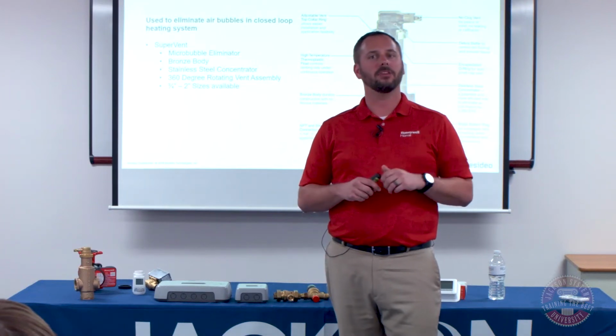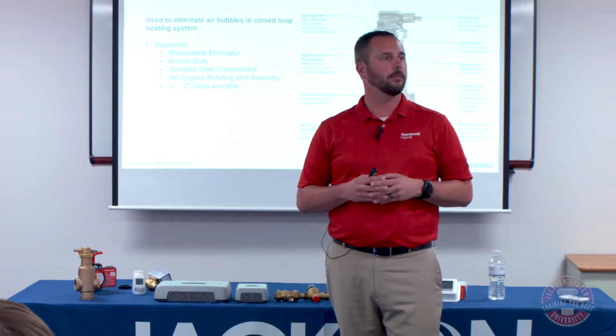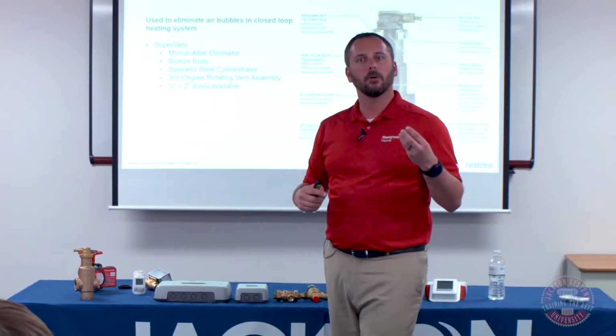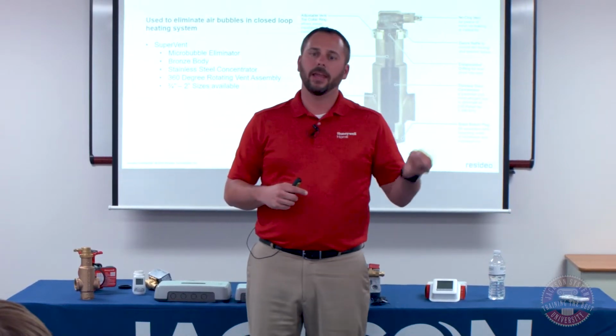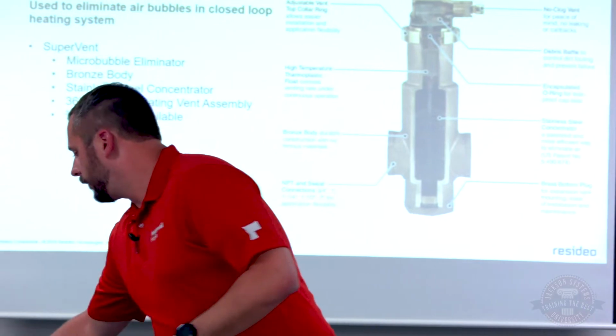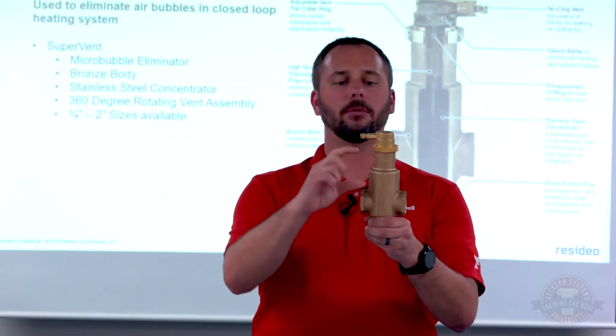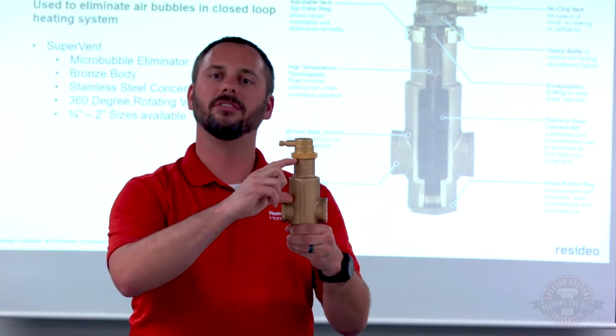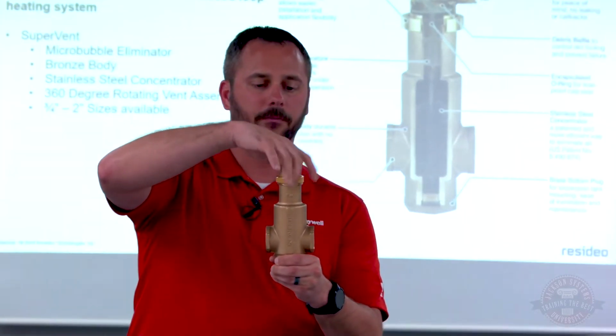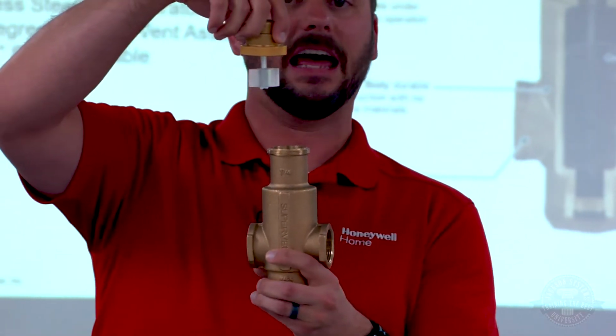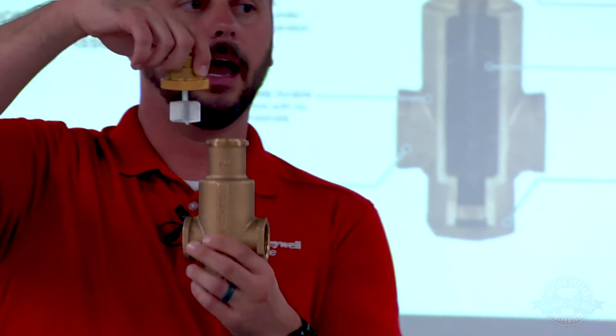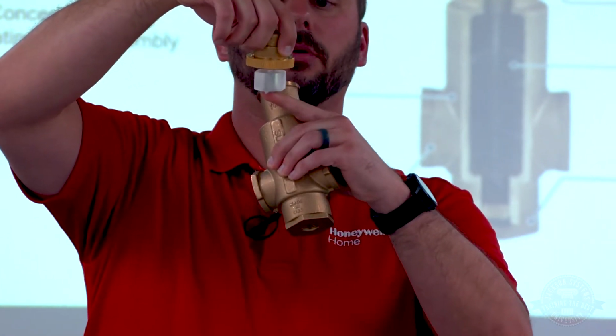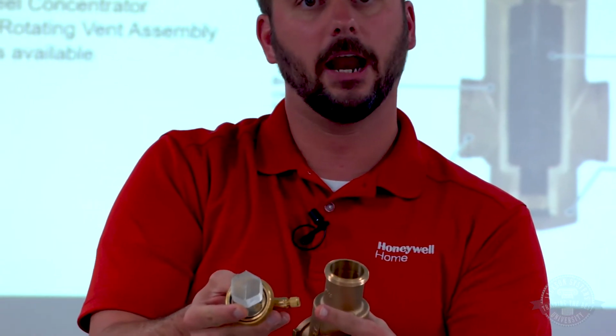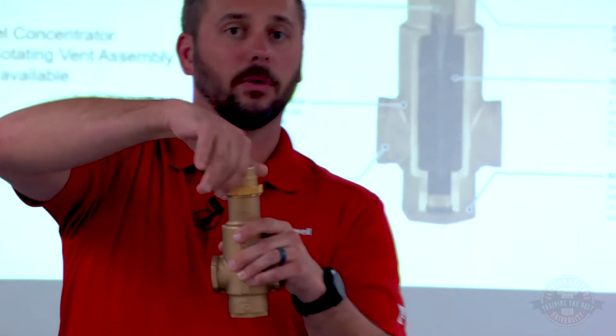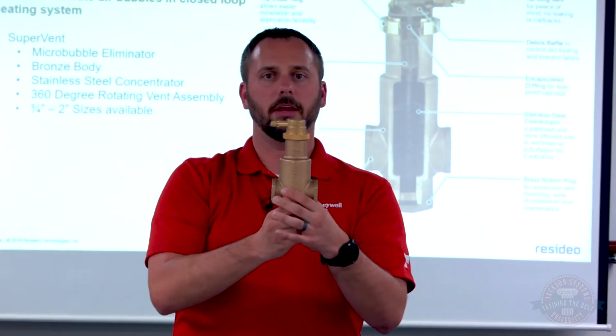What happens with this is we have a coalescing media that looks like a stainless steel brush inside of it. As the water passes through here, any of those micro bubbles get stuck on those bristles, and they end up purging their way up to the top. Once those micro bubbles start to come up, you've got a big collection area here where they come inside of this device. Inside of here, we have a big plastic float. This is solid all the way throughout. As the air comes in and gets collected, it pushes this float up to the top. There's a mechanism inside of here that opens this up, and it bleeds the air out of the tip. This can also be replaced, serviced, etc., but it's an incredibly reliable air vent.